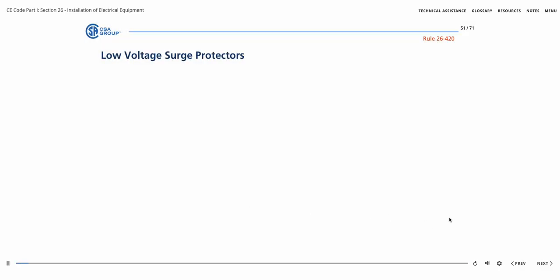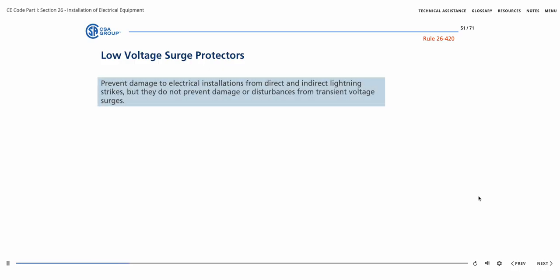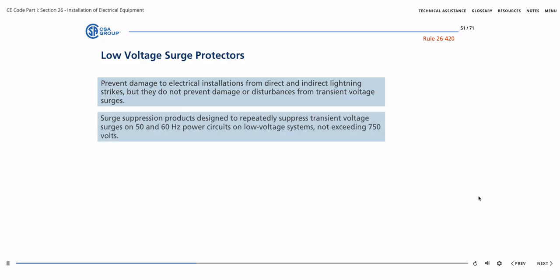A transient voltage surge is a momentary voltage surge on a signal or power line that lasts for a short time. It can produce false signals or triggering impulses and cause insulation or component breakdown and failures. Rule 26-420 addresses low voltage surge protectors and requirements for safe use. Lightning surge suppressors have been used successfully for many years to prevent damage to electrical installations from direct and indirect lightning strikes, but they do not operate fast enough to prevent damage or disturbances from transient voltage surges. Low-voltage surge protection devices, or transient voltage surge suppressors, are surge suppression products designed to repeatedly suppress transient voltage surges on 50 and 60 Hz power circuits on low-voltage systems, those not exceeding 750 volts.